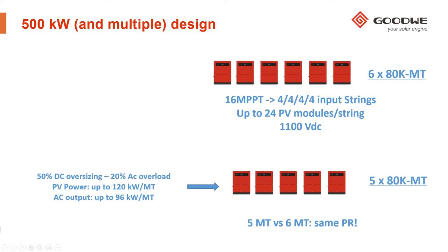But we also want to give you a suggestion to use only 5 devices instead of 6. According to our PVSYST calculation, you get the same performance ratio by using this combination. And you should take into account that the MT80K has a capability of up to 50% DC oversizing and up to 20% AC overload. So for a 500 kilowatt project, you can definitely use also this combination, which is an additional saving for you.